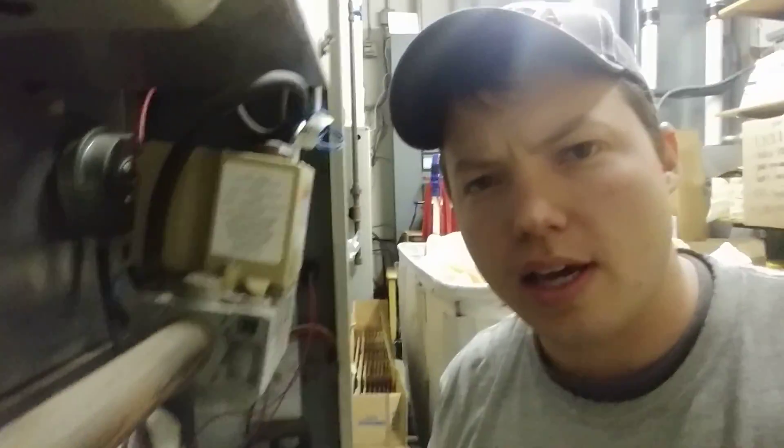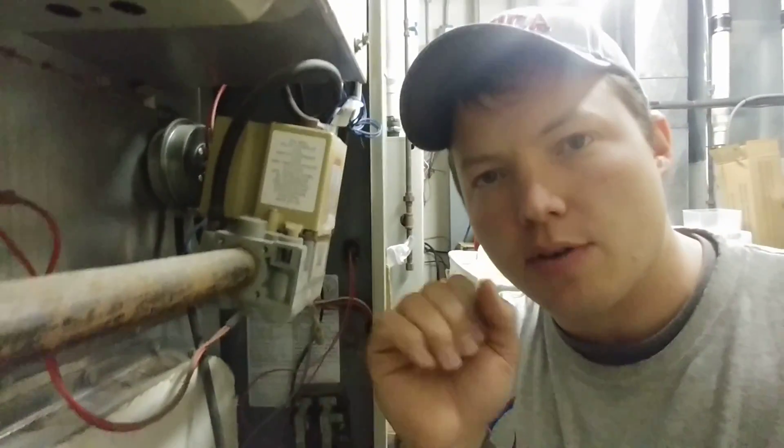There you have it — that's what it looks like. You can see those flames are rolling back, and eventually this box here just gets too hot and that sensor trips out, because it's not supposed to get very hot. Those flames are supposed to pull through there straight.